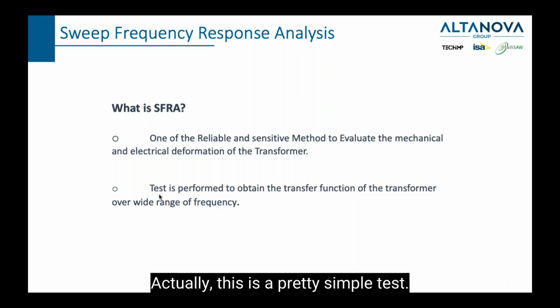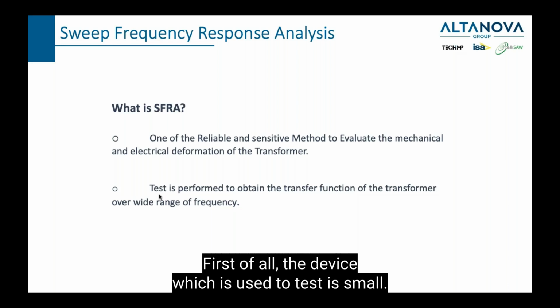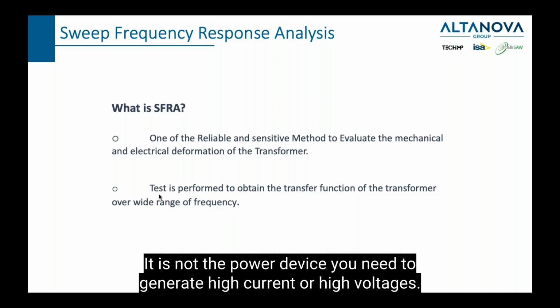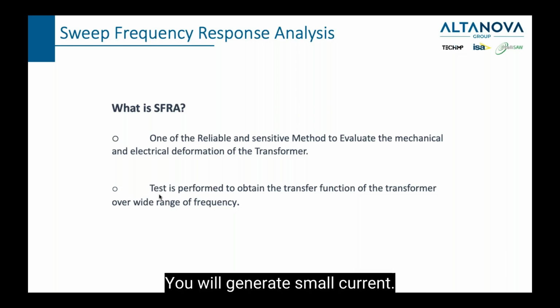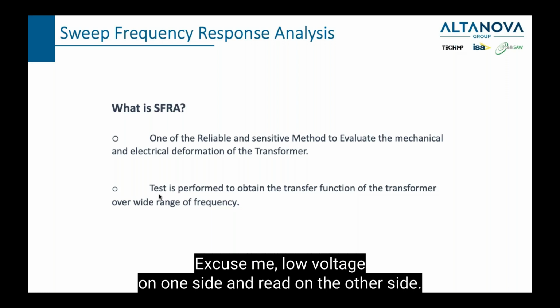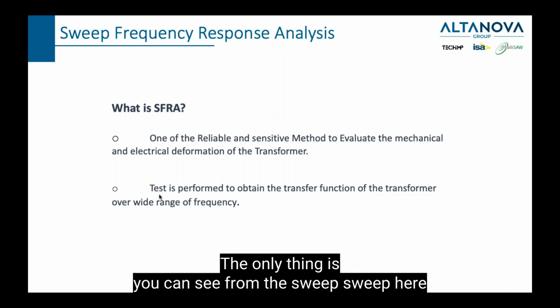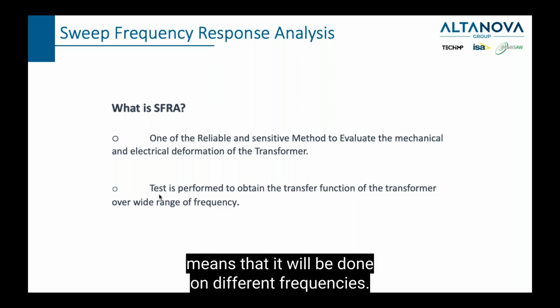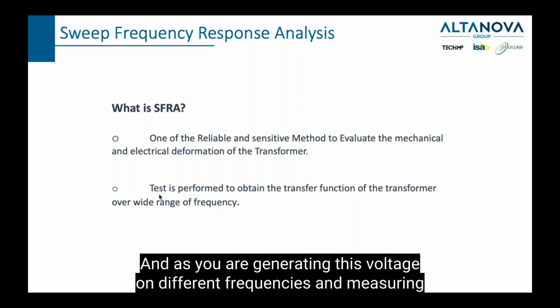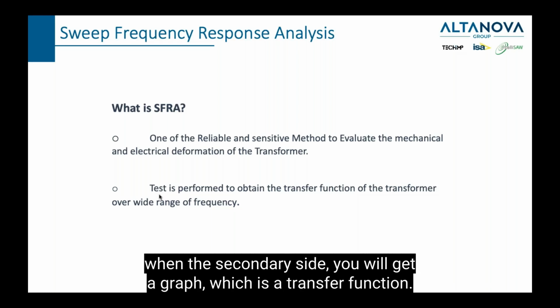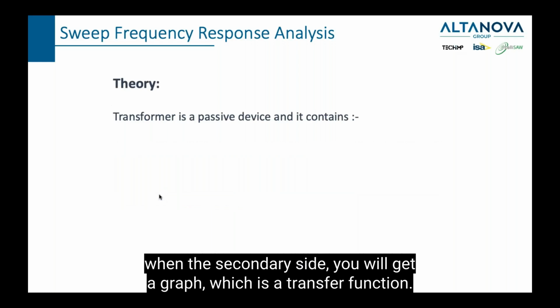Actually, this is a pretty simple test. First of all, the device which is used to test is small. It is not a power device. You don't need to generate high current or high voltages. You will generate small current, low voltage on one side, and measure on the other side. The only thing is, as you can see from the name, sweep. Sweep here means that it will be done on different frequencies. And as you are generating this voltage on different frequencies and measuring on the secondary side, you will get a graph, which is a transfer function.